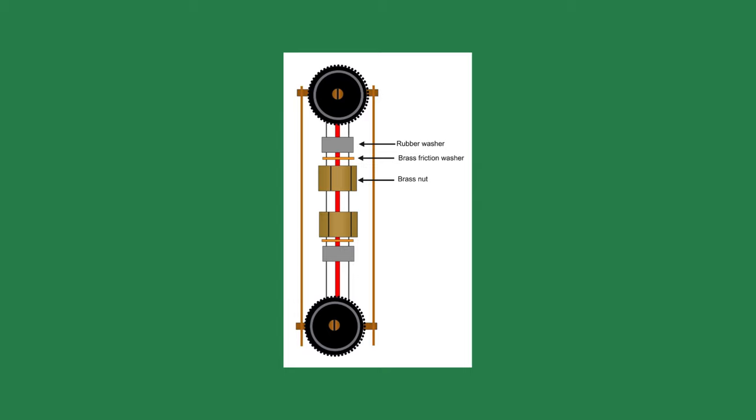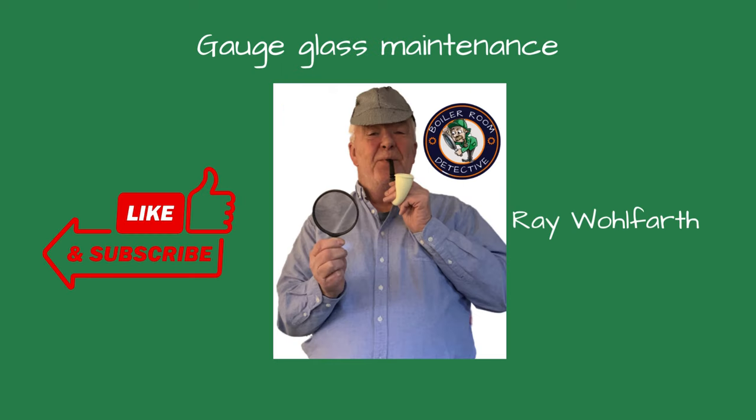After rinsing the inside and outside of the tube, when replacing the gauge glass, start by sliding the brass nuts onto each end facing opposite directions. Next come the brass friction rings, then the rubber washers. Be sure to leave about an inch of glass above and below the rubber washers. Lift the gauge glass into the top of the valve — you should be able to slide the bottom into the lower valve and let it drop down. Carefully slide the rubber washers and nuts down over the threads and tighten slowly. Replace the vertical brass rods and open the valves. You should see water inside.